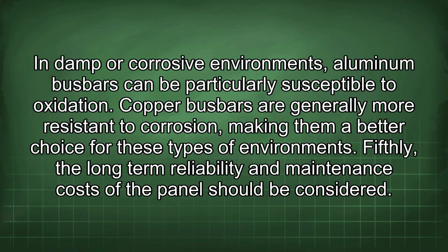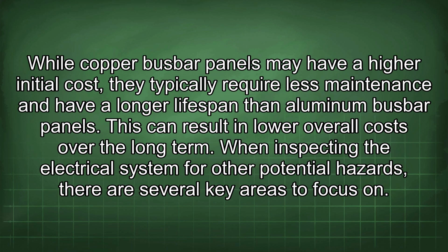Fourthly, the environmental conditions in which the panel is installed can also play a role. In damp or corrosive environments, aluminum busbars can be particularly susceptible to oxidation. Copper busbars are generally more resistant to corrosion, making them a better choice for these types of environments. Fifthly, the long-term reliability and maintenance costs of the panel should be considered. While copper busbar panels may have a higher initial cost, they typically require less maintenance and have a longer lifespan than aluminum busbar panels. This can result in lower overall cost over the long term.